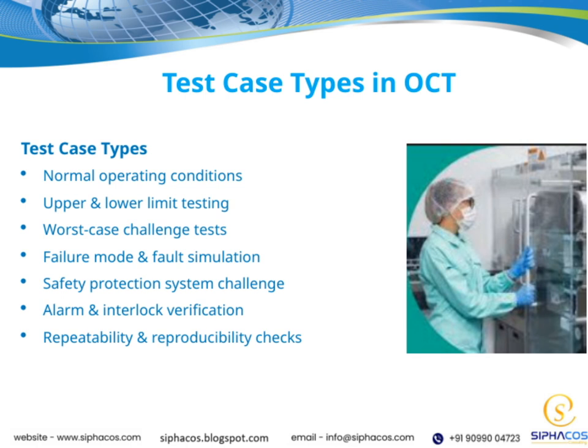Then, there are worst-case challenge tests, designed to push the system to its limits in challenging scenarios, ensuring robustness. We also perform failure mode and fault simulation, where we intentionally introduce faults to see if the system correctly detects and manages them. Safety protection system challenge tests are crucial. They verify that safety mechanisms activate properly under fault conditions to protect both the system and users. Alarm and interlock verification checks that alarms trigger appropriately and interlock mechanisms engage when necessary, preventing unsafe operations. Lastly, repeatability and reproducibility checks ensure that tests produce consistent results over multiple runs, confirming reliability over time.